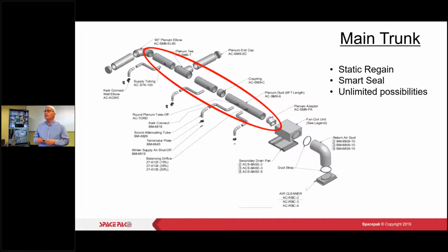Main trunk. We want you to use the 9-inch round. If you can't, or if you have ductwork available or a metal shop, you can do the equivalent. That's not a problem, as long as it's the equivalent of 64 square inches, we're good to go. But what's nice about our 9-inch spiral round ductwork is that it has seals, gaskets on it. So when we put it together, it's a sealed connection and it's not going to leak. So you want to take advantage of that.